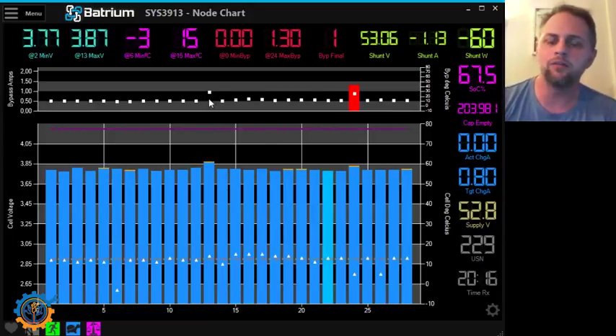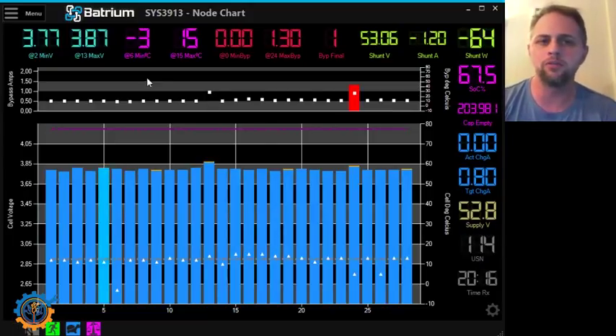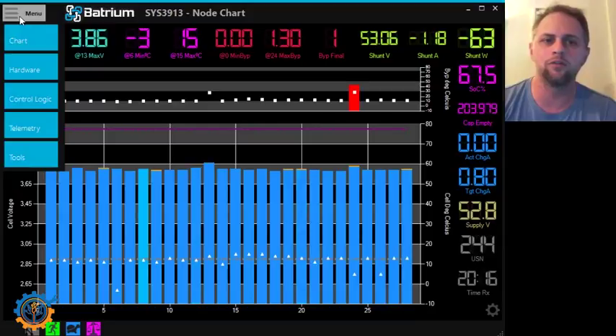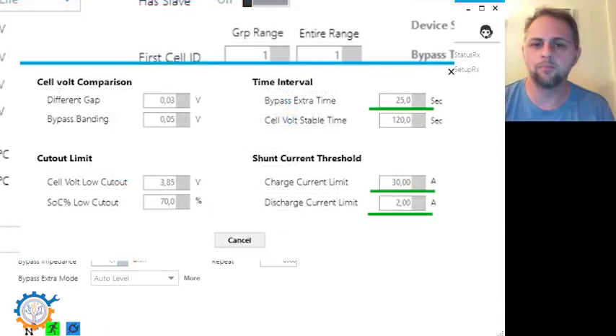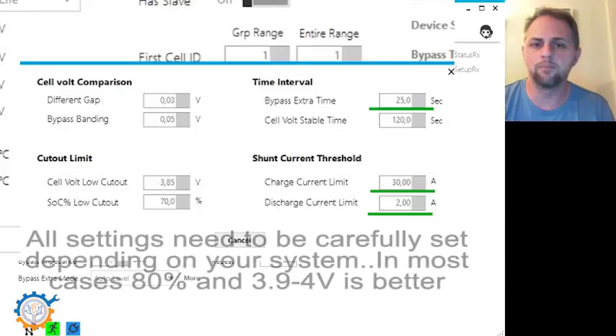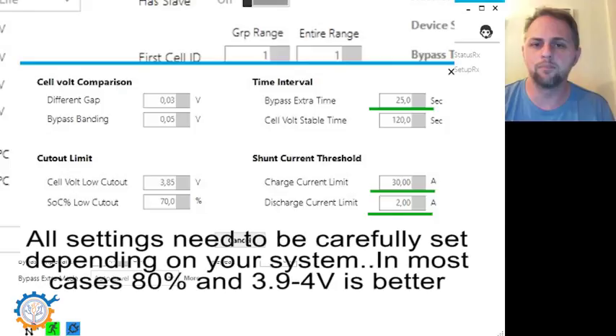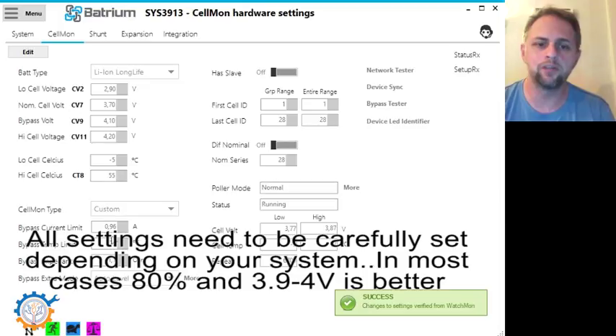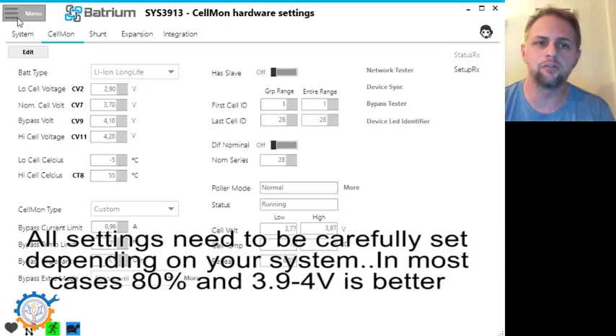So this guys is how the balancing is working. It's a nice feature but you need to set it up correctly for it to do what you want. Recommended values of state of charge, this depends a little bit. I would say you need to be above 70% for this to actually be properly. So in this pack I'm actually running 70% and the voltage 3.85 perhaps. I will leave the different gap and bypass banding because I think those values are good and the shunt threshold as well. And we save it. By saving this the bypass turns off again.